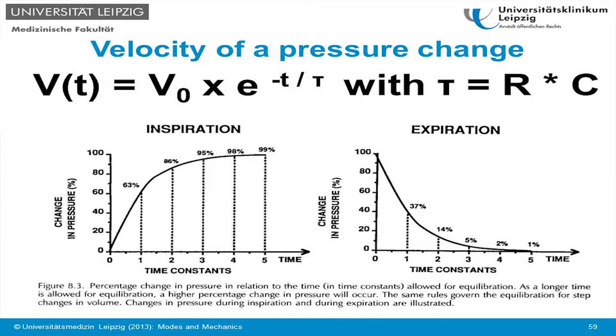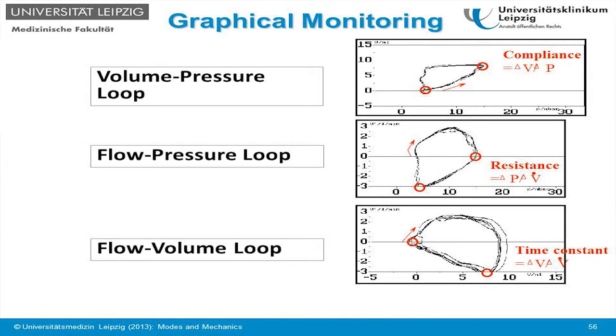And so if you know the resistance and the compliance, you can calculate the time constant and get an idea of how inspiratory and expiratory times may optimally be set for your individual patient. And also with the third loop, I'll show it again, with the flow volume loop, you can also directly measure the time constant by measuring this slope here.